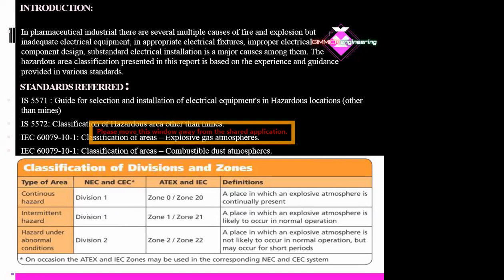I'll start with some introduction to hazardous area classification. Hazardous classification is a method of analyzing and classifying the environment where explosion of gases or atmosphere may occur. It takes into account the ignition characteristics of the gas or chemical, normally referred to in chemical terms as fume or vapor. The ignition energy, referred to as gas group, and the ignition temperature are the two main contributing factors to hazard or flammability.